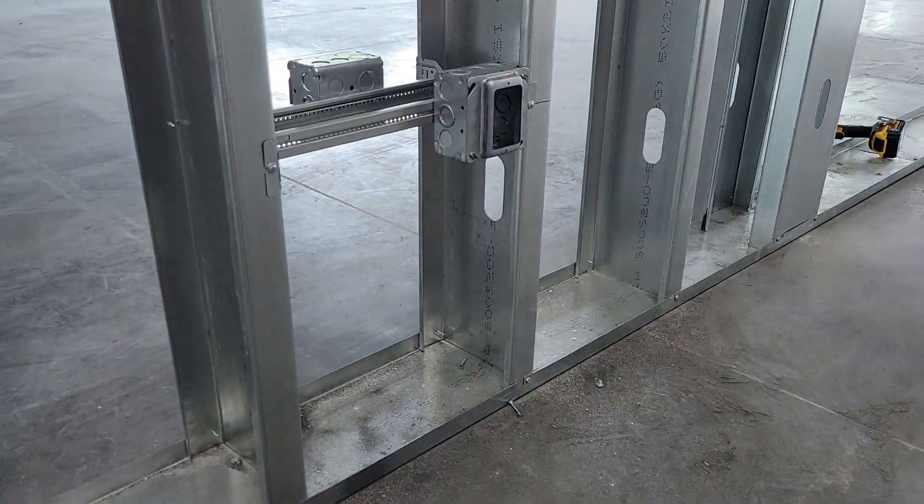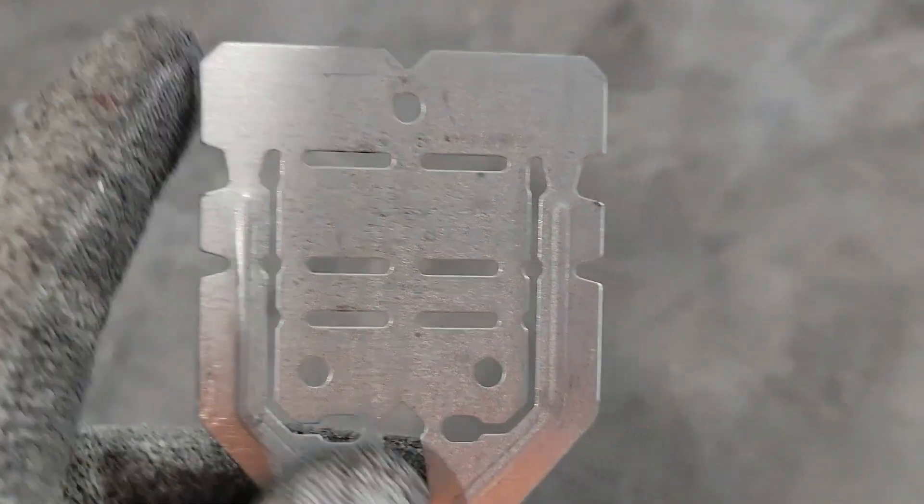At the top it says two and a half, down here it says one and a half. Your regular four square boxes are two and an eighth deep, so what you do is you bend this up like this.